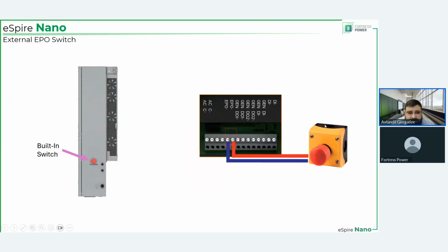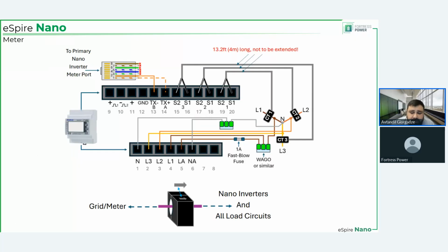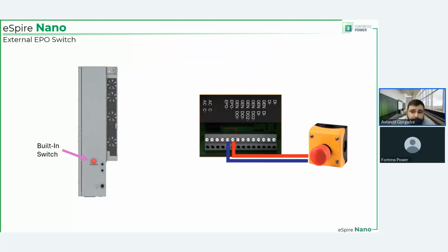So EPO plus, EPO minus, this is what I meant. Built-in switch right here. Both of them are active. If either one is activated, rapid shutdown and the EPO of the inverter is initiated. And one more thing. Initiating EPO on the inverter doesn't mean that the EPO will be initiated on the battery. I just want to make that very clear. We're going to develop a solution on how to make it so that one button initiates the EPO on both. But in a normal configuration, with the inverter connected to the battery, communication being there, power cables being there, auxiliary AC being there, pressing one of the EPO buttons doesn't activate EPO on both units.